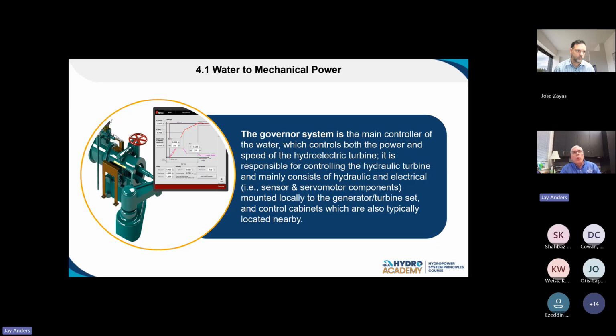Once our unit gets tied to the electric grid, we parallel across our generator breaker. We synchronize all of our ABC phases so they're totally in phase with what's going on out in the electric system. The grid is so big, it dictates what speed your unit's going to turn at, namely 60 hertz. Whatever frequency it was operating at before it got online, as soon as it ties into the system, it is at 60 hertz. The system demands that, and the speed may slow down or pick up a little bit depending what goes on. And it's that speeding up or slowing down that's where the kilowatt load comes into play.